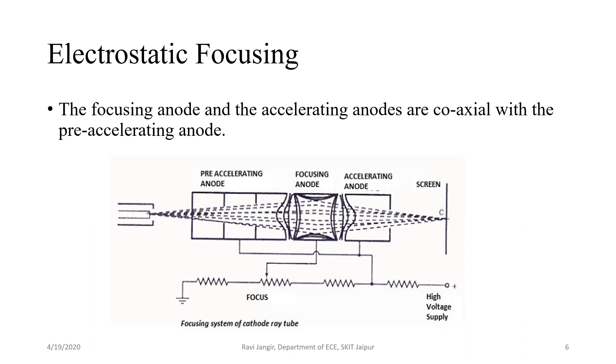The figure shows electrostatic focusing arrangement for CRO. As we can see that the electron beam which is coming out of control grid is a bit scattered. Now to focus this beam to the center of the screen, we need a focusing arrangement. In this focusing arrangement, we use three anodes that is pre-accelerating anode, focusing anode and accelerating anodes. The focusing anode and accelerating anodes are coaxial with the pre-accelerating anode.